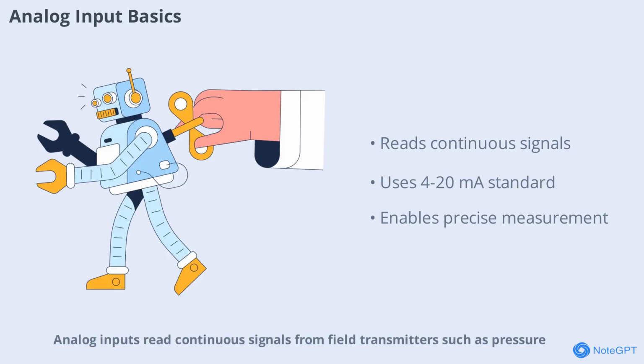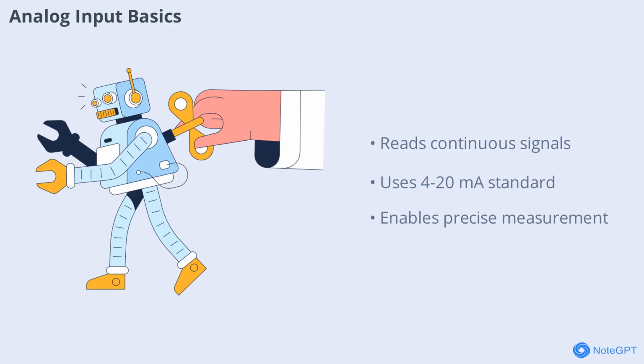Analog inputs read continuous signals from field transmitters, such as pressure, temperature, flow, or level sensors. These signals typically use the 4-20 mA standard, allowing precise measurement of process variables. Analog inputs provide the detailed information needed for advanced control strategies and monitoring. Understanding how analog inputs work is crucial for accurate system performance and troubleshooting.